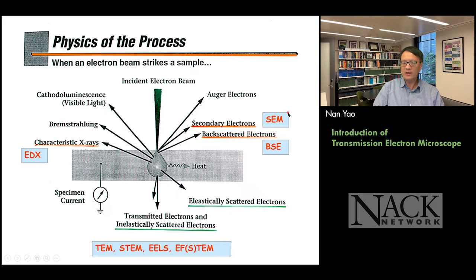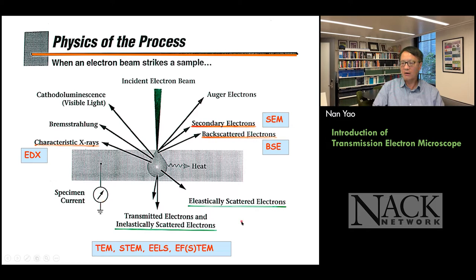For instance, we're probably already familiar with the SEM. Using secondary electrons, we can study the morphology of the material. Backscattering electrons let us study orientation of materials. Characteristic x-rays can tell us what kind of elements are inside your sample from the region your probe is in. If the incident beam energy is high enough and the sample is thin enough, all the signals can penetrate through the sample. That is the foundation of transmission microscopy. For TEM, you're using electrons — electron transmission through the sample generates all kinds of signals after the sample. That's the base of transmission electron microscopy.